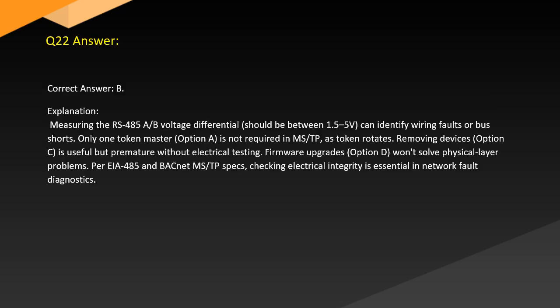Answer. Correct answer: B. Explanation. Measuring the RS-485 voltage differential can identify wiring faults or bus shorts. Only one token master, option A, is not required in MSTP as the token rotates. Removing devices, option C, is useful but premature without electrical testing. Firmware upgrades, option D, won't solve physical layer problems. Per RS-485 and BACnet MSTP specs, checking electrical integrity is essential in network fault diagnostics.